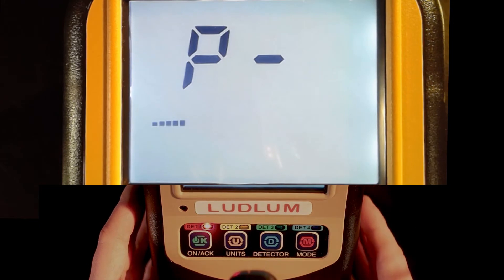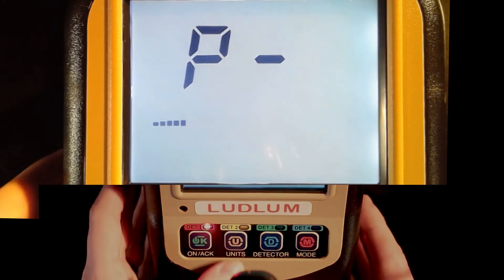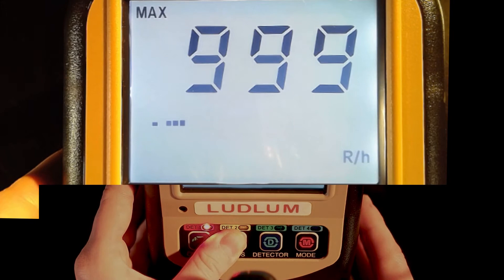Press the MODE button to go to page 2. Press the UNITS button three times to get to the alarm setting.